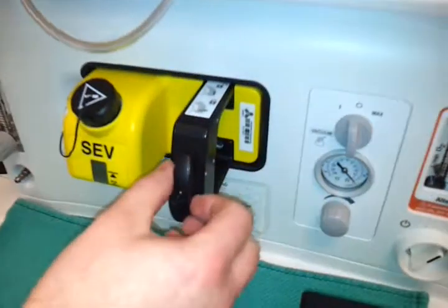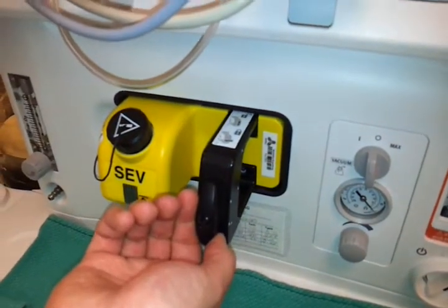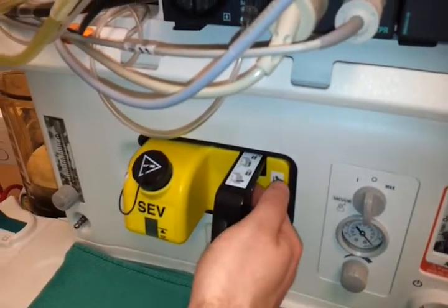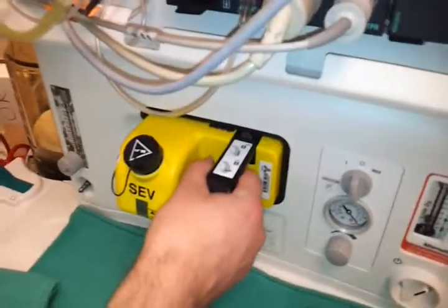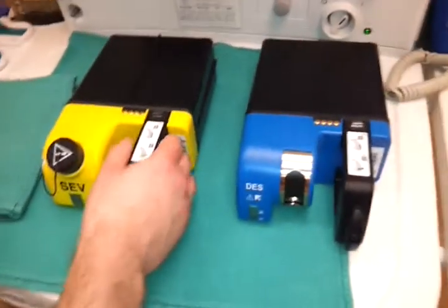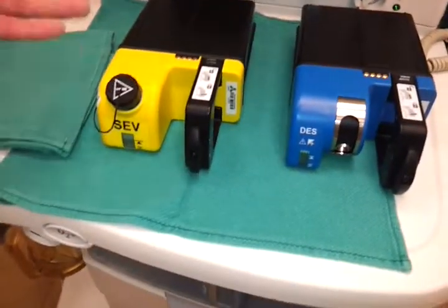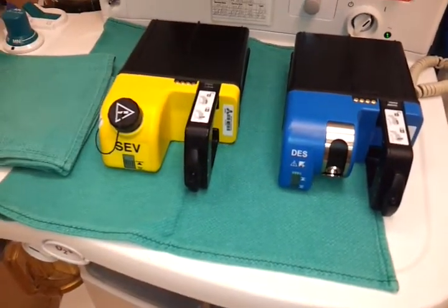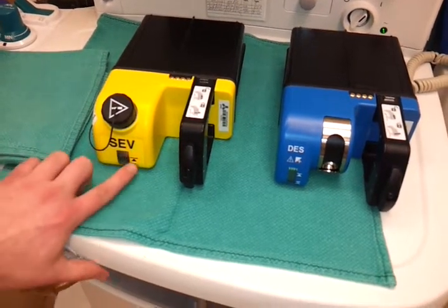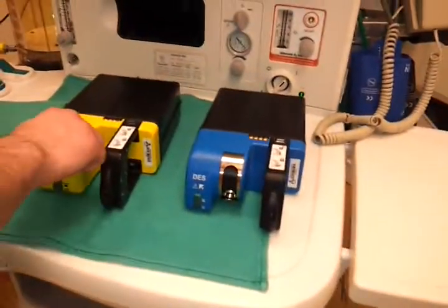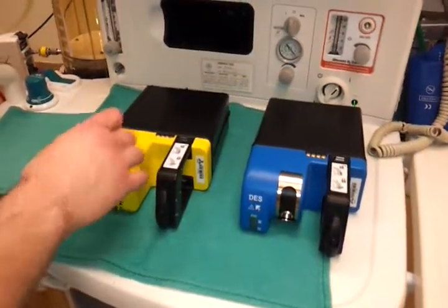The next thing you want to do is check your anesthetic gases. So you want to take them out. To take them out, you just turn this little lock here, and there's a little trigger in the back. You just pull the trigger and it pops out. So you want to set it on a flat surface to check the level, and to check the level you want to just make sure that the gas is lined up with the top line here. You can see that on both of them. These are full, but I'll just show you how you would fill them if you had to.